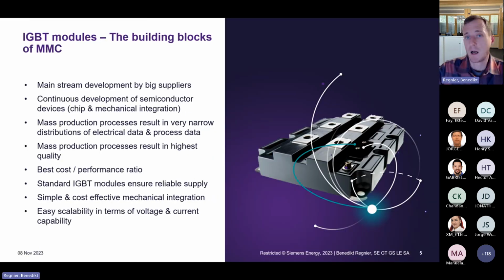Yeah. How do we build our HVDC? So the real core of the VSC is the IGBT. And what we are using here is not really a super special, super sophisticated HVDC IGBT. It's a standard IGBT. And this makes it really good, because then this core element is broadly available. And also HVDC is growing fast and it's big, but looking at the market, it's still a small area. So whatever device you're using, which is solely developed for HVDC, it makes it a bit complicated.